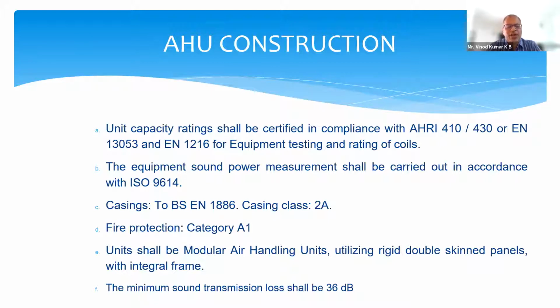The next important thing is, when you have AHUs running, you feel a big noise coming from the air handlers. Now, we can't have noise, because noise control is going to be an important part, especially in critical areas like the theater or the ICUs. A doctor giving an instruction to a nurse, or to a technician, has to be well heard. There should be a sound level which is acceptable, and the manufacturers have to follow the standards of ISO 9614. Similarly, when you come to the AHU's construction, it's a big box, and the box has a casing. The outside casing is supposed to follow BS-EN 1886. These standards are to be set up in your specifications, which you will be issuing to your vendor before you select the product.